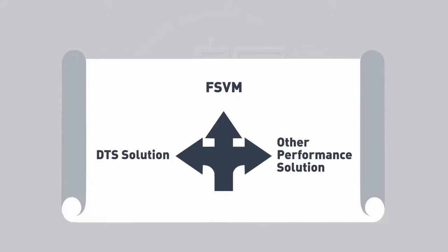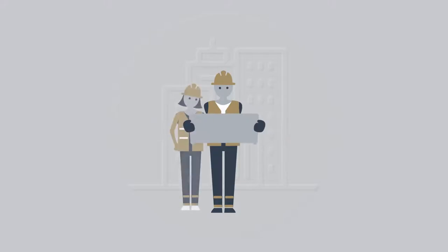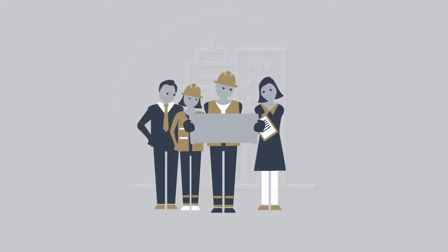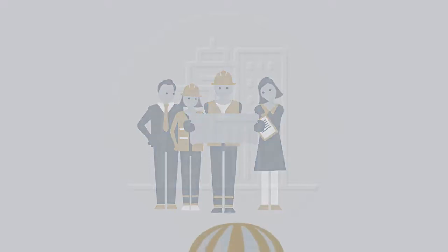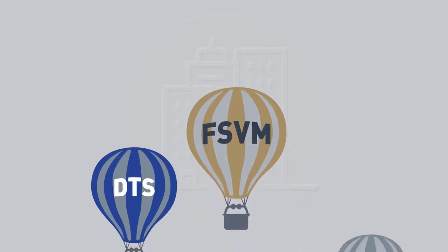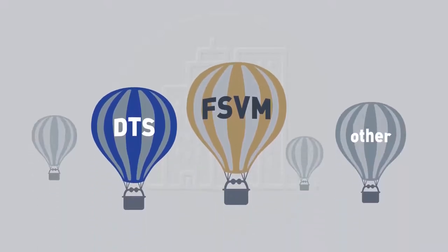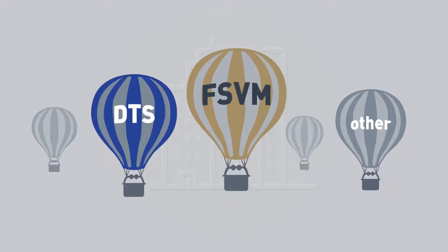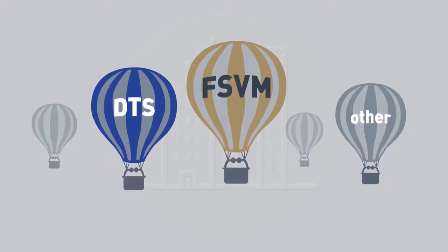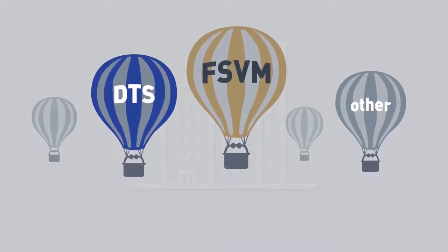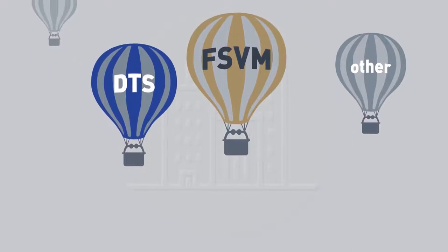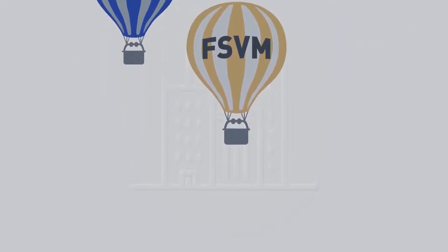Remember, the verification method is just one way of developing fire safety solutions. The level of fire safety achieved using this verification method must be at least equivalent to the relevant NCC Volume 1 Fire Safety DTS provisions. The verification method sets out a process to develop a performance solution for fire safety.